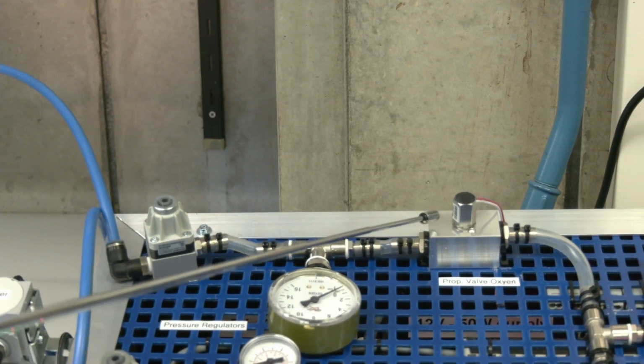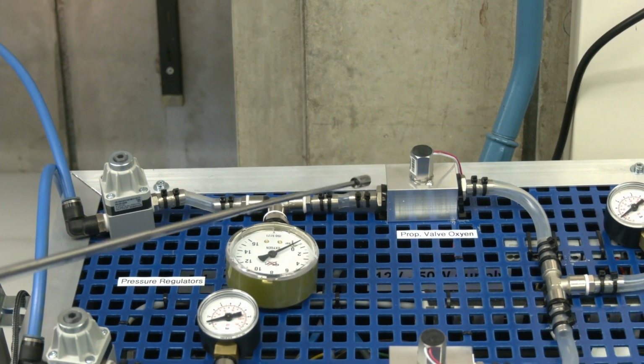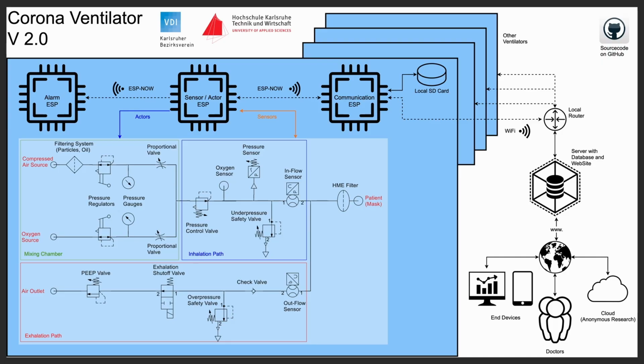To perform the mixing task, each line is followed by an electrically driven proportional valve, with which the flow of the individual gases can be adjusted. By controlling the valves anti-proportionally, the oxygen concentration can thus be adjusted between 21 and 100%. The oxygen level of the respiration air mixture is measured with a galvanic O2 sensor.